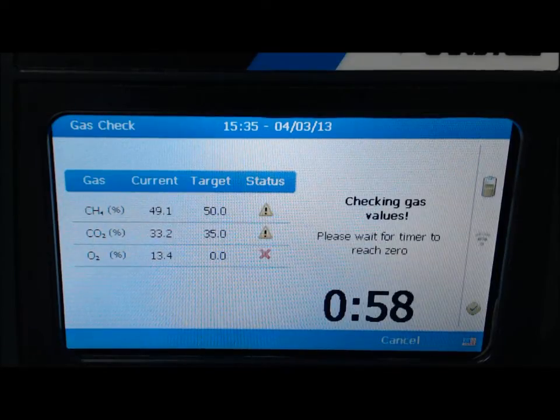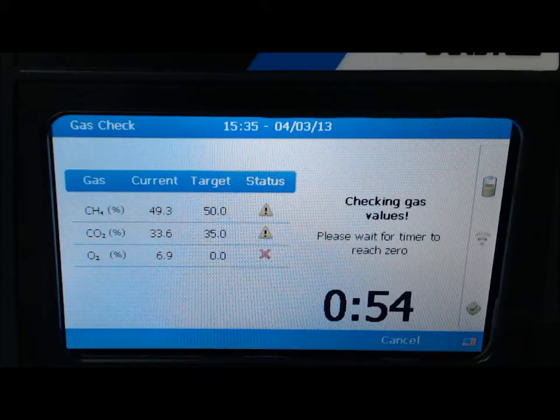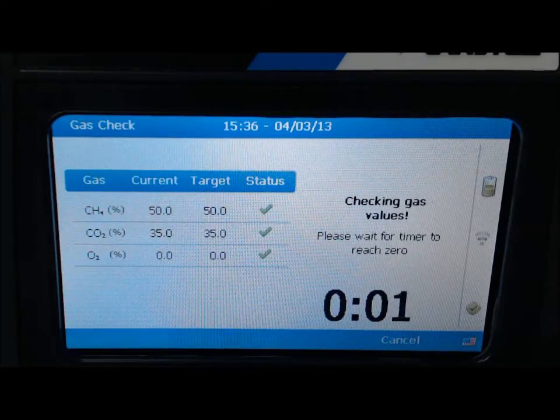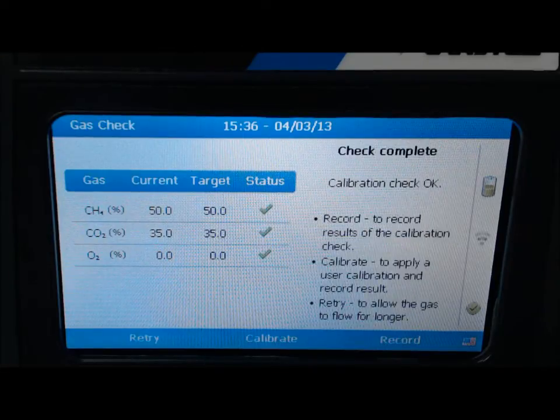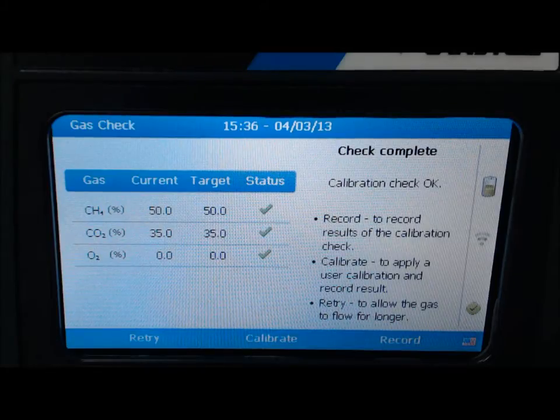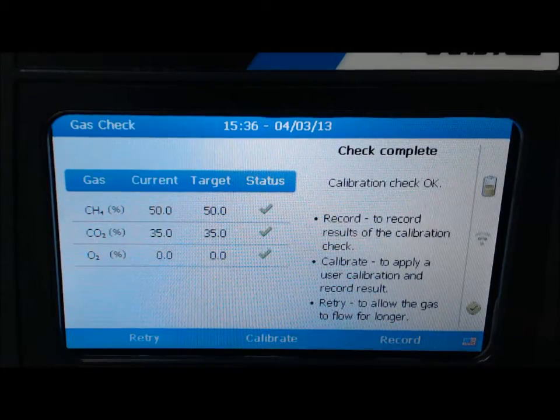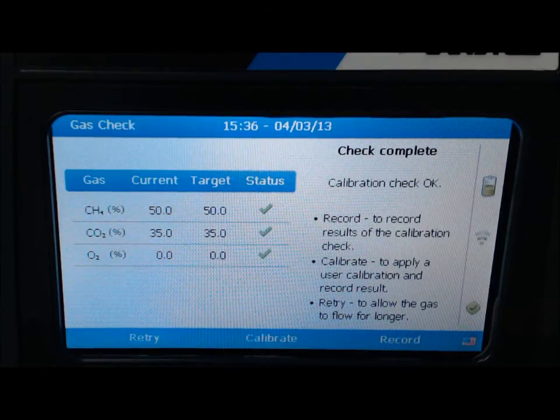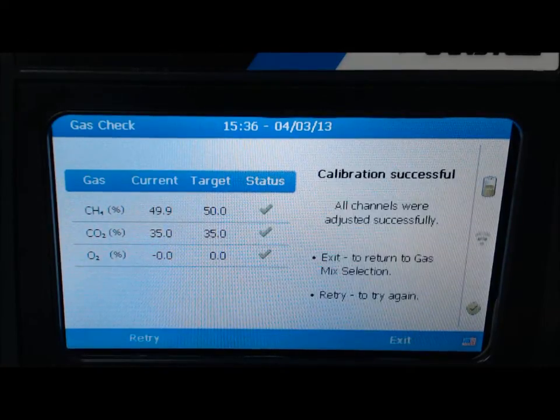A 1-minute timer will start for readings to stabilize. When the timer reaches zero, the following message will be displayed: Check complete. Once again, read the status field and select calibrate to span the CH4, CO2, and O2.